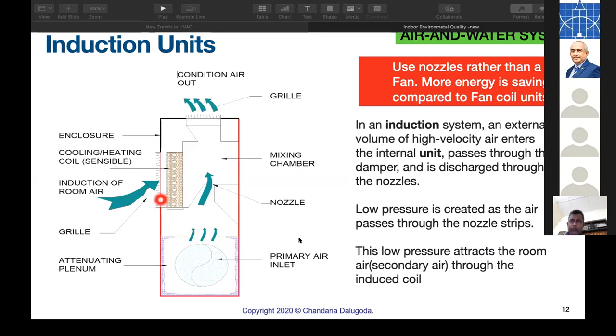Now, beside the grill, you have a single cooling coil. Now, that is a sensible coil. What is a sensible coil? It's kind of a passive coil, no fan. Sensible coil means the surface temperature is above the dew point temperature of air. Now, this absorbs only the sensible part of the room. Water vapor will be absorbed by the primary air.